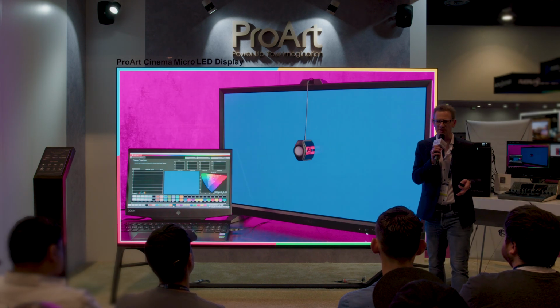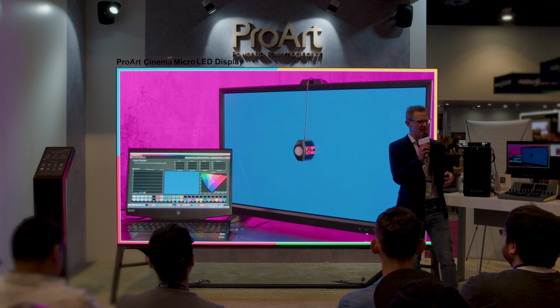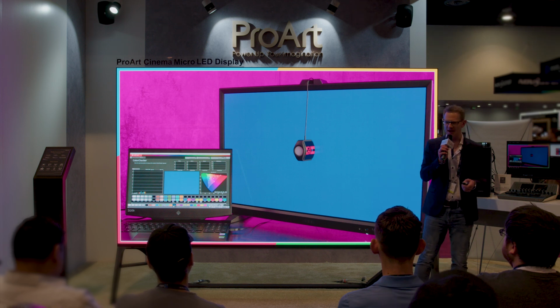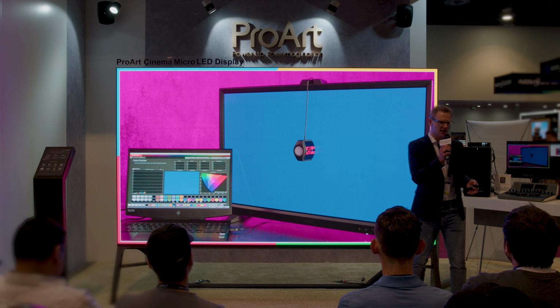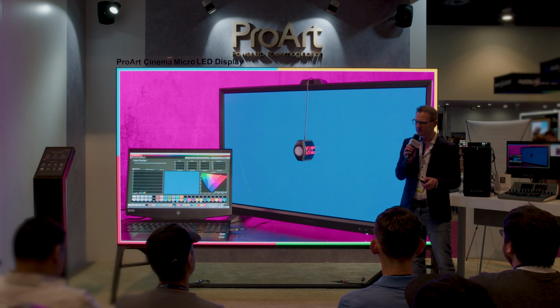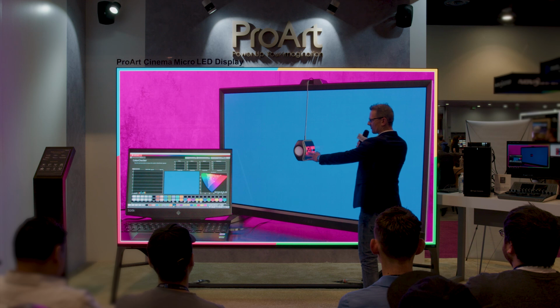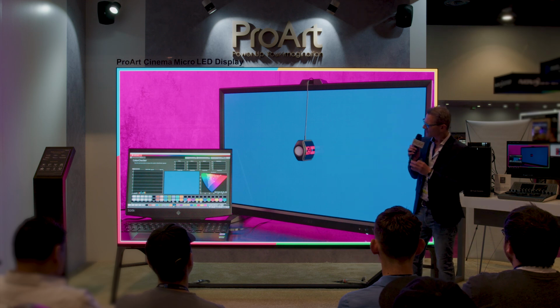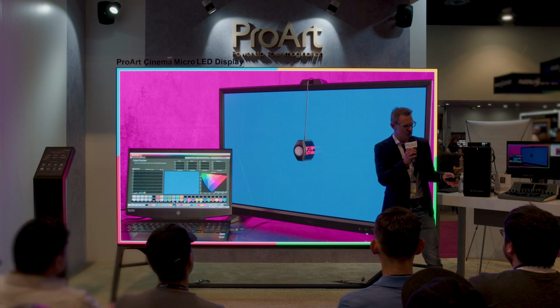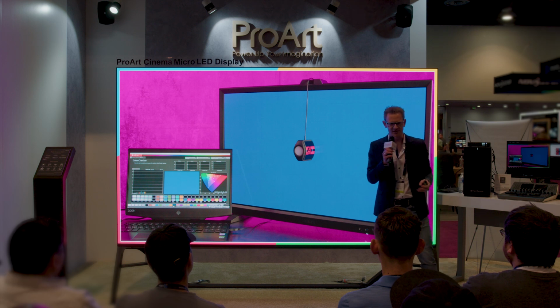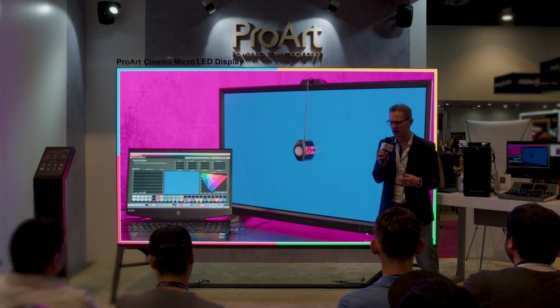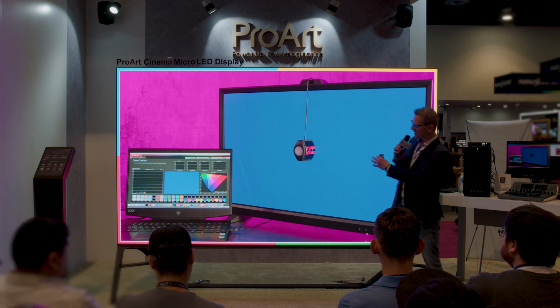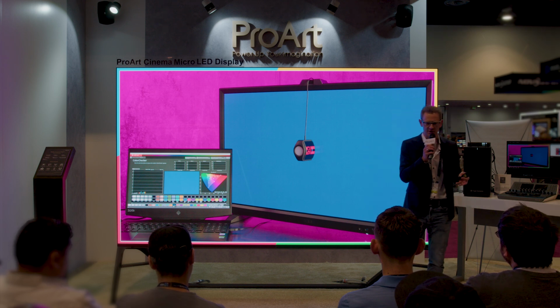And in the calibration process, what we normally do is we actually have a reference and we're comparing the reference with what the display is doing. Now, how are we going to do this? Well, we need a meter. This is this kind of probe in the center you see on the screen, and that takes the readings off the screen. So we have a software, in this case, our Calman software, that's controlling the meter, and it's also controlling a pattern generator.